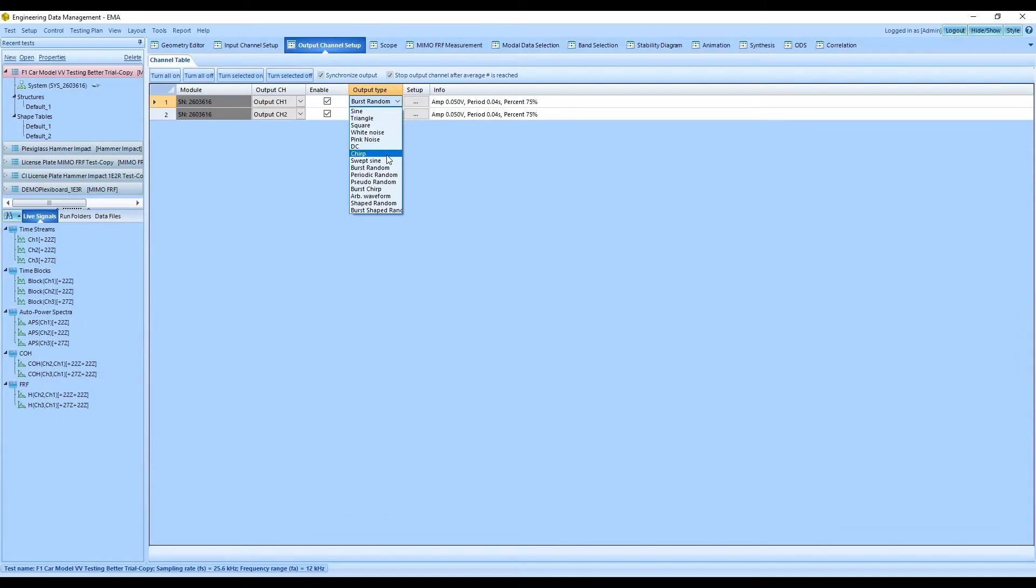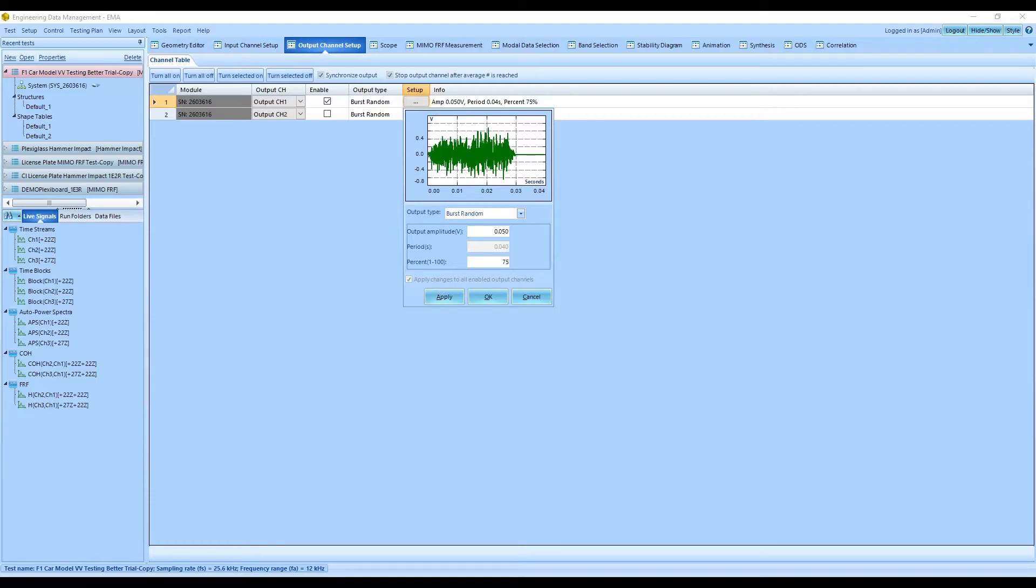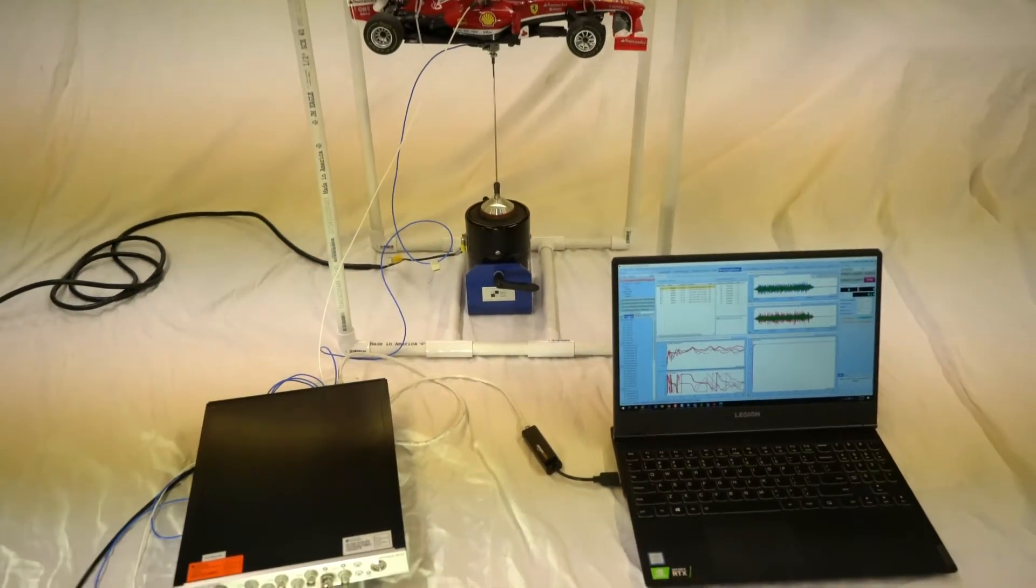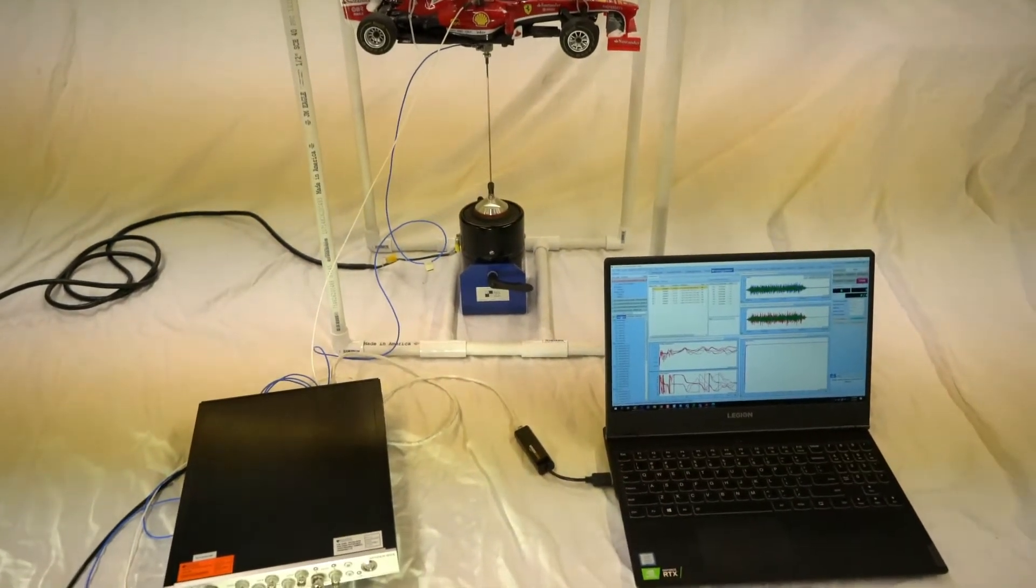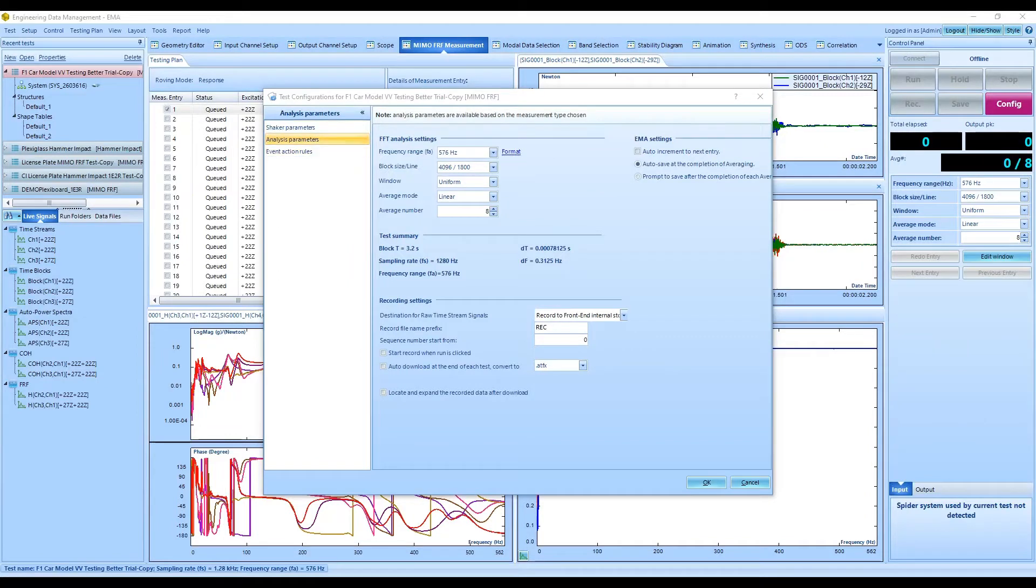The input channels are configured for the impedance head and accelerometer. Burst random output excitation is selected for this modal test setup. The FFT settings are configured accordingly for the modal measurement process.